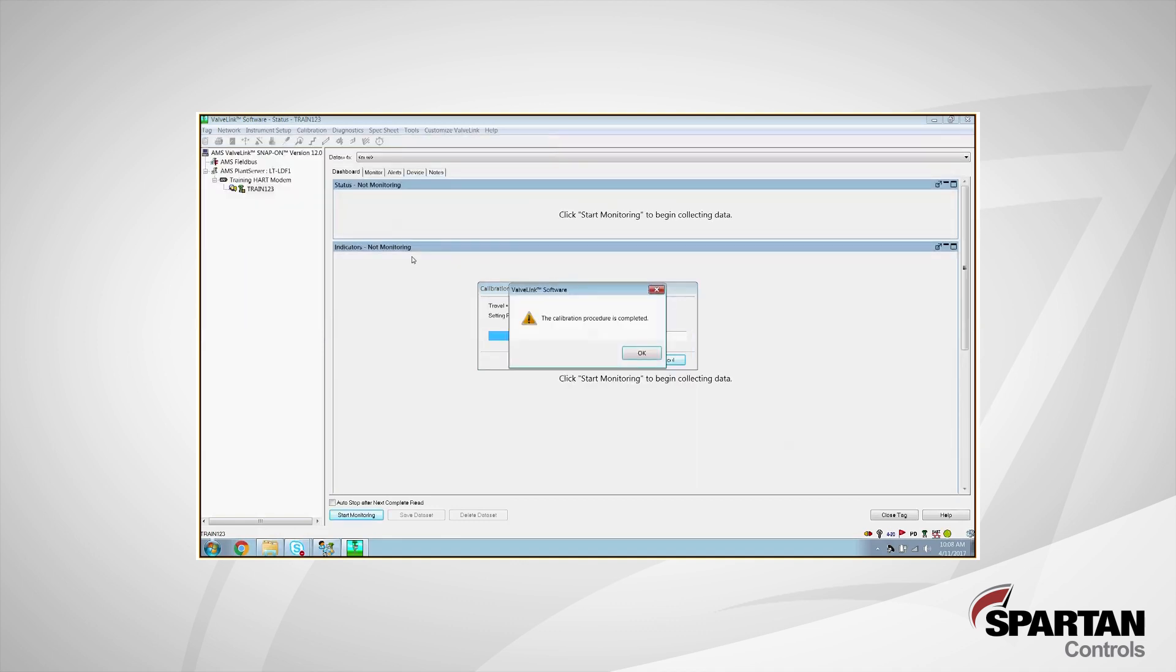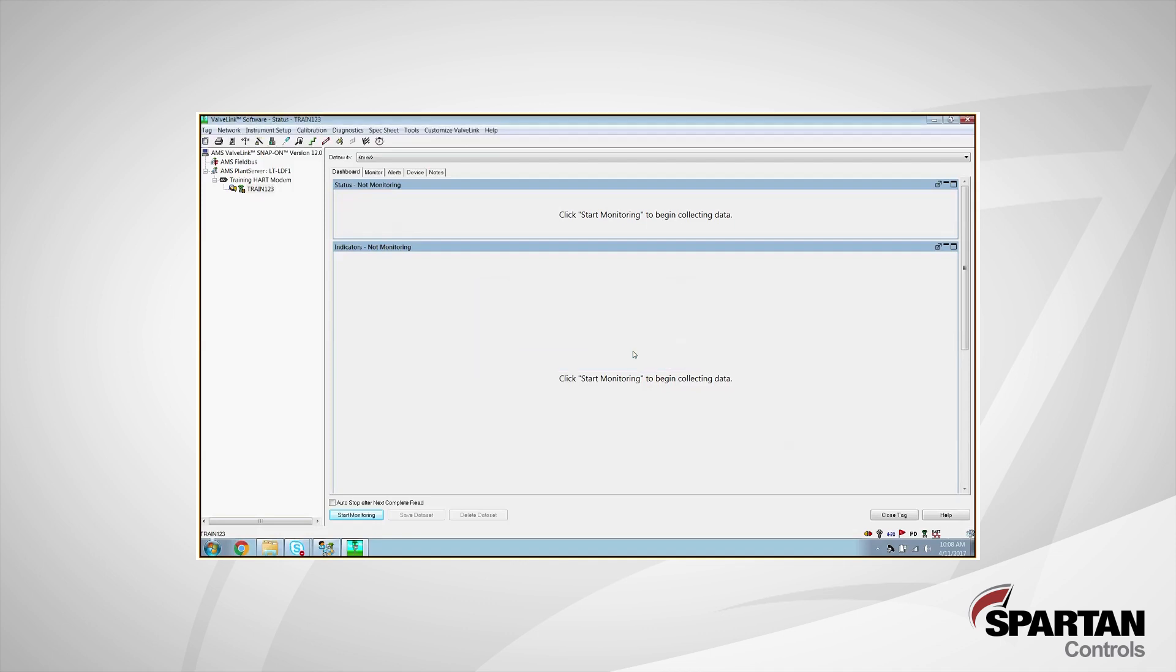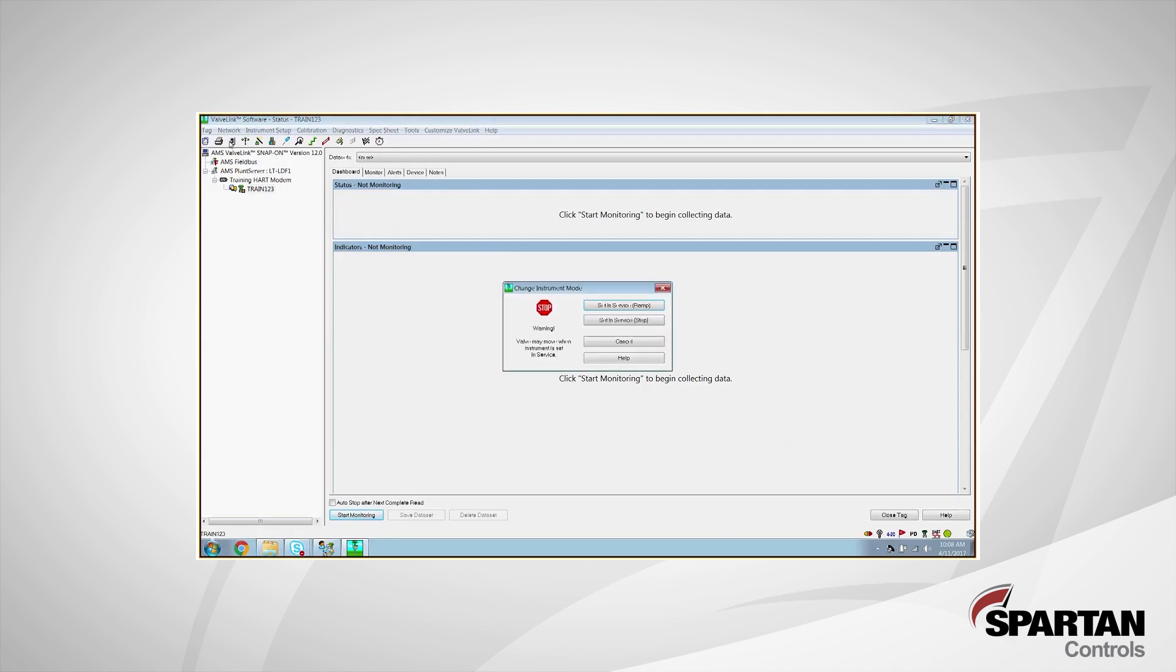And there we have it. Our calibration is now complete. Our DVC will be fully functional at this point. But if you do have extra time, it's always a good practice to go in and fill out your detailed setup and your spec sheet. But otherwise, if you're just looking to get your DVC working, all you have to do at this point is put it back into service. I can do that easily in the top left here where this little light switch is that says instrument mode. Click on that guy and we're going to set it back into service.